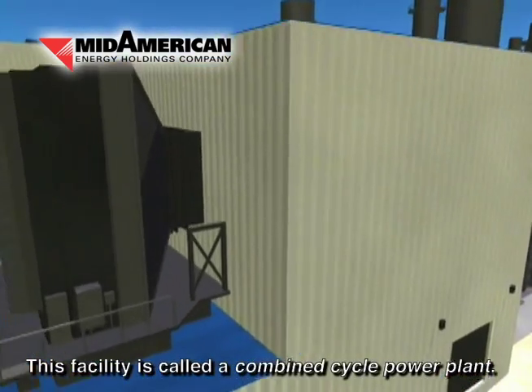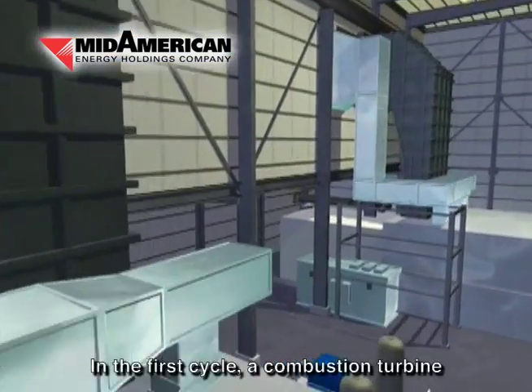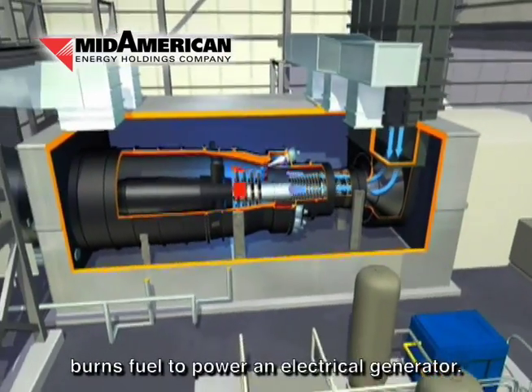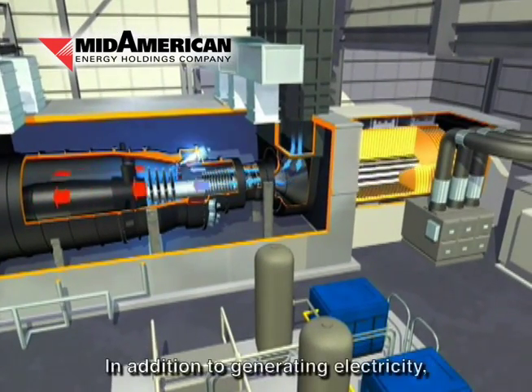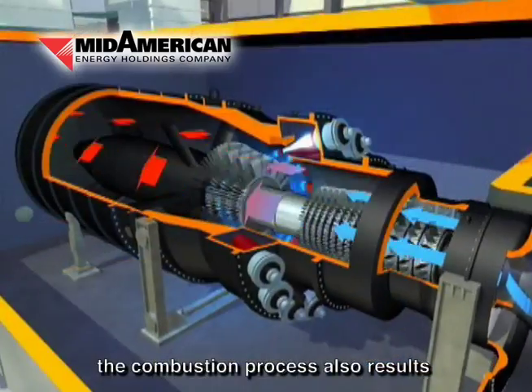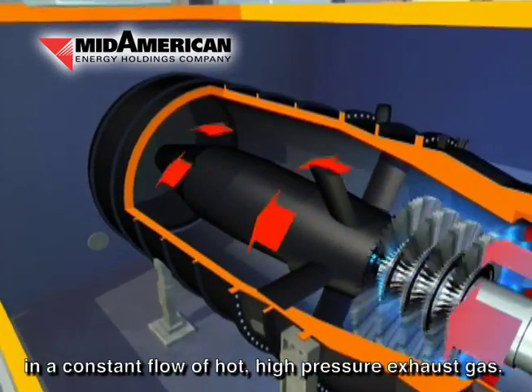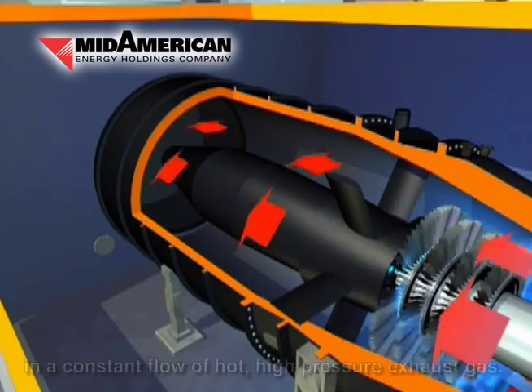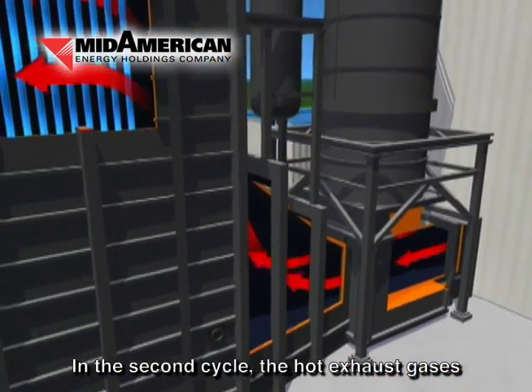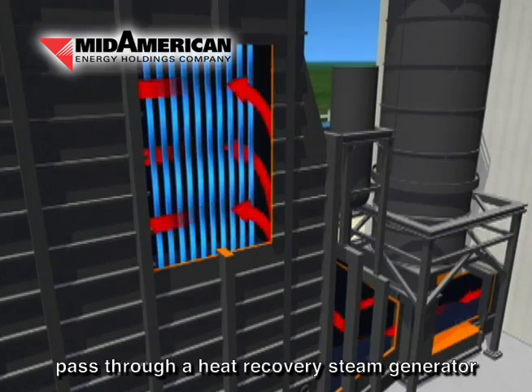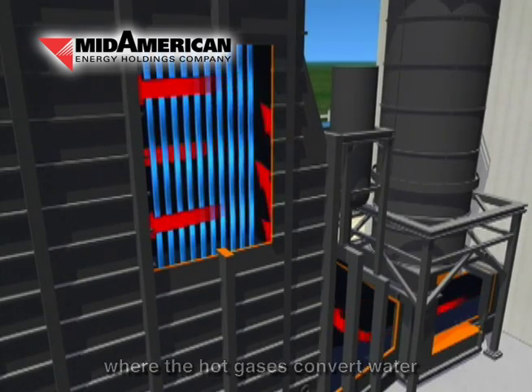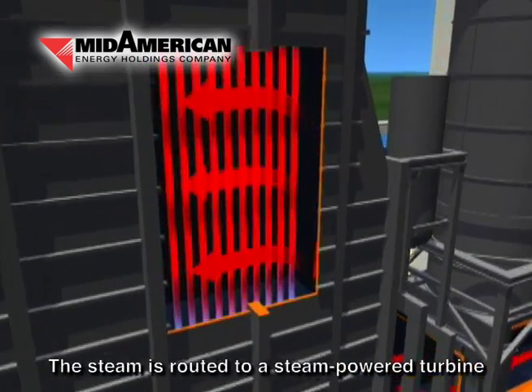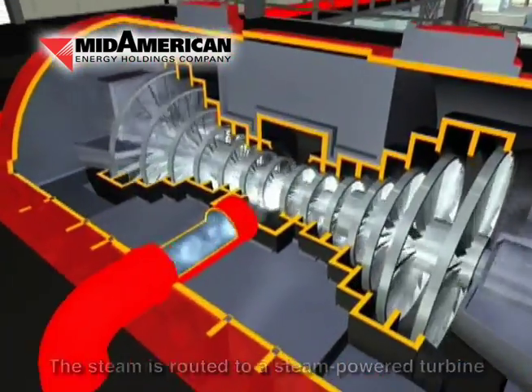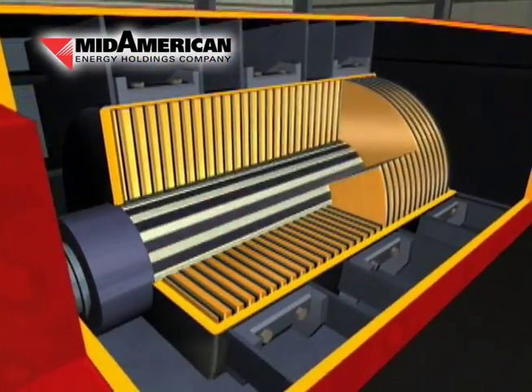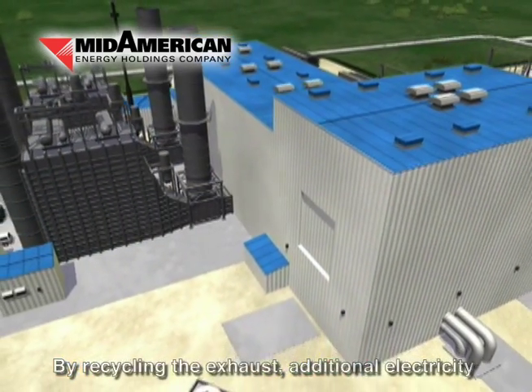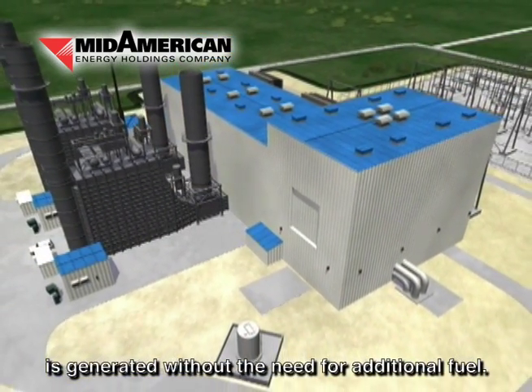This facility is called a combined cycle power plant. In the first cycle, a combustion turbine burns fuel to power an electrical generator. In addition to generating electricity, the combustion process also results in a constant flow of hot, high-pressure exhaust gas. In the second cycle, the hot exhaust gases pass through a heat recovery steam generator, where the hot gases convert water into high-pressure steam. The steam is routed to a steam-powered turbine, which powers another electrical generator. By recycling the exhaust, additional electricity is generated without the need for additional fuel.